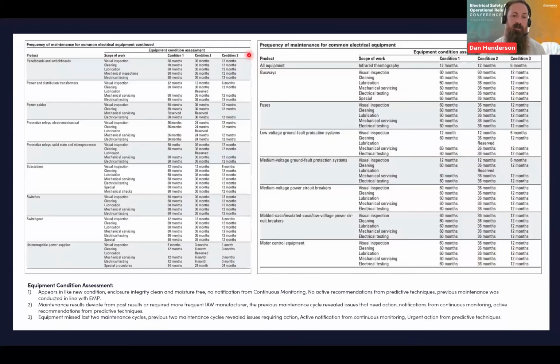So just to clarify those points for those that aren't familiar, within NFPA 70B, there's these 3 different conditions. So condition 1, which you'll see has got the longest frequency, for example, 60 months or 5 years, is where the equipment appears like new condition. The enclosure integrity is clean and moisture free. There's no notification from continuous monitoring, so any online monitoring systems you might have. And there's no active recommendations from any predictive techniques. And the previous maintenance that was done was conducted in line with the electrical maintenance plan. So essentially, it's been maintained when it should. You've got no flags or alarms. It looks good. It looks like new, and all's well in the world. So in fairness, we can come back to that within 60 months. That's fine. That's what, from a prescriptive approach, we would be looking at.